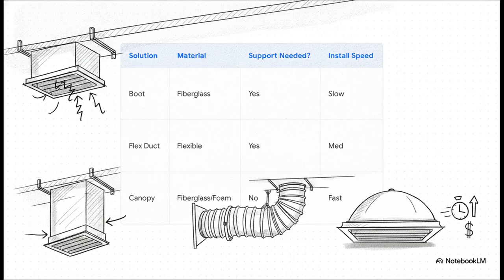Option 2 is grabbing a length of flexible duct and attaching it to the grill, leaving the other end open to the plenum. This also needs structural support so it doesn't just collapse on itself. But the third solution? That's the canopy. Made from fiberglass or foam, this thing is incredibly lightweight. It just sits directly on top of the return air grill without any extra support at all. It completely blocks the line of sight into the ceiling, comes in standard sizes, and because it installs so quickly, it's pretty much always the fastest and cheapest option. It's a real game changer.